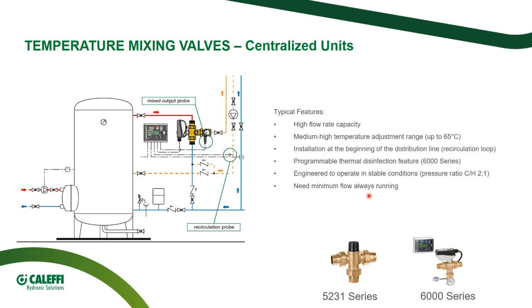Some of them have programmable thermal disinfection features. We are speaking, for instance, about the Caleffi 6000 series Legiomix. They can be programmed to perform the thermal disinfection throughout the whole recirculating loop. Such type of valves are engineered to operate in stable condition with a fixed mild pressure ratio between hot water and cold water that is maximum 2:1. They always need a minimum flow always running through them in order to be stable and efficient.